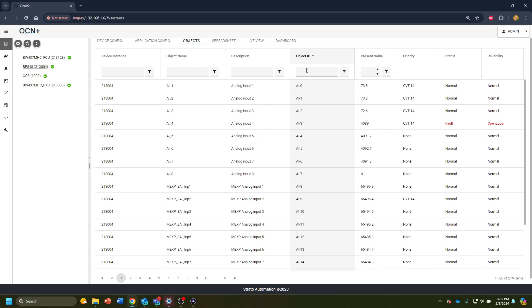If I right click on one of my objects, let's say I want to look at AVs, and I want to see AV H2 here, AV29, which is my outside air. Now I don't have a temperature probe hooked up here, but if I right click on this, I can edit the present value. Let's say I want to simulate what it's going to be like to get my economizer to start working or to lock up my compressors. We can override this by setting the priority to whatever value I'd like, enter the value, and hit apply, and you'll see it show up in the tree.